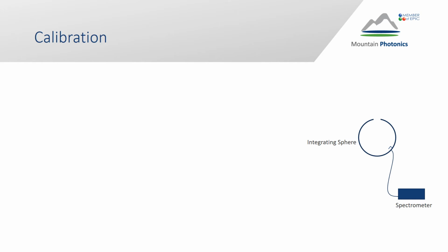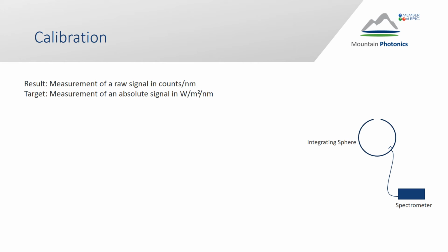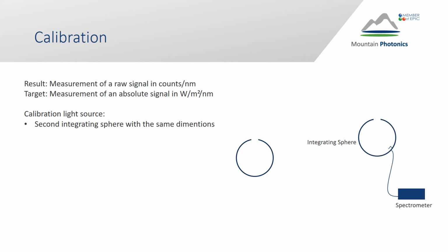Now, with this measurement setup, we are able to measure a raw signal in counts per nanometer, assuming that the spectrometer already has been calibrated for nanometers. But what we are going to measure is an absolute signal in watt per square meter and nanometer. And that's why the whole measurement setup needs to be calibrated for absolute irradiance. Therefore, we are using a calibrated light source. There are different kinds of calibrated light sources for irradiance calibration, but we are using a second integrating sphere with exactly the same dimensions as the measurement sphere. So with the same port diameter and the same sphere diameter. But this time with internal halogen bulbs and a constant current driver.